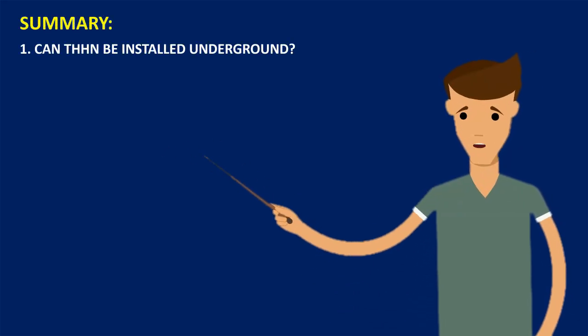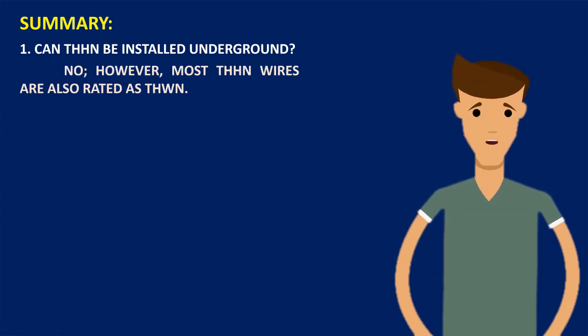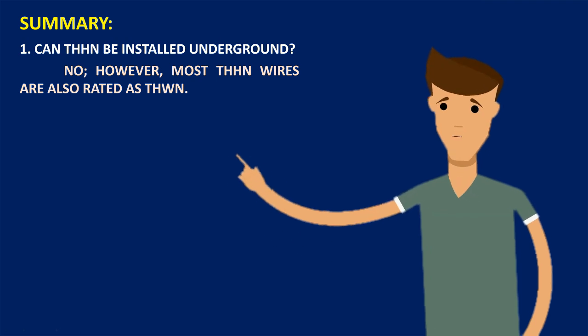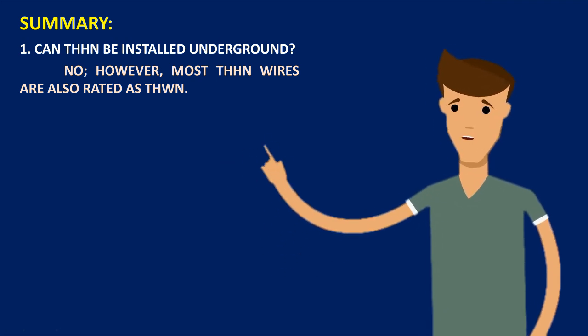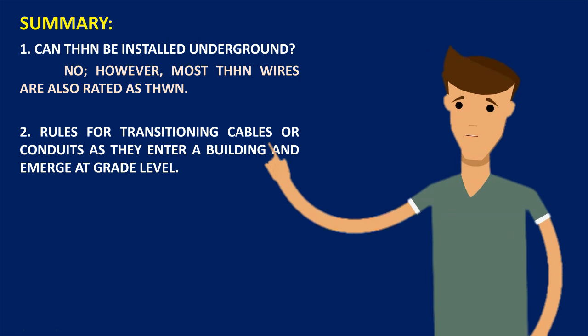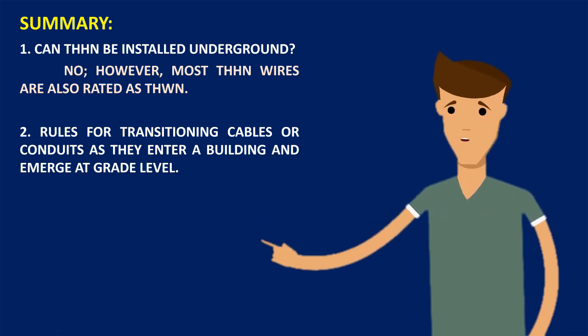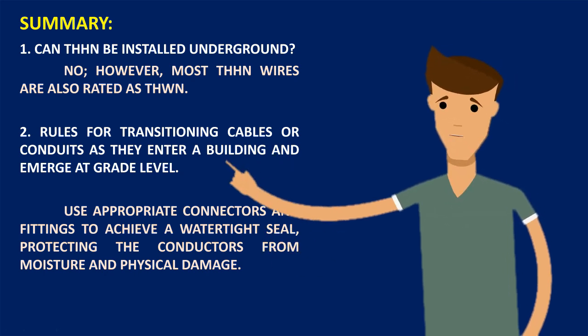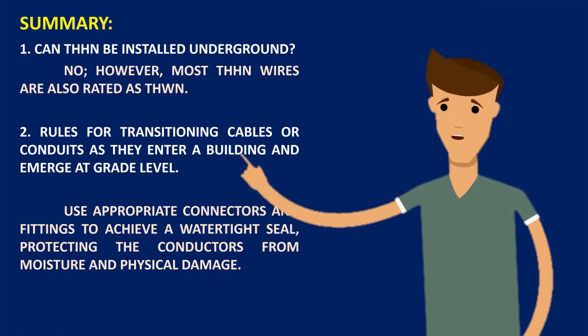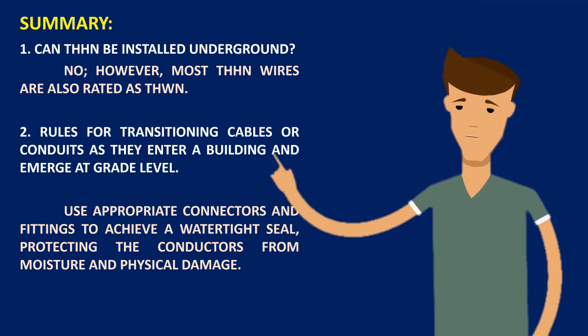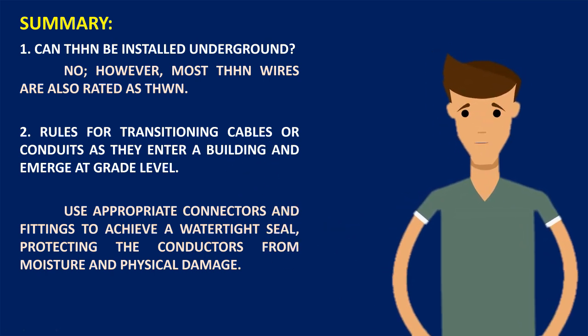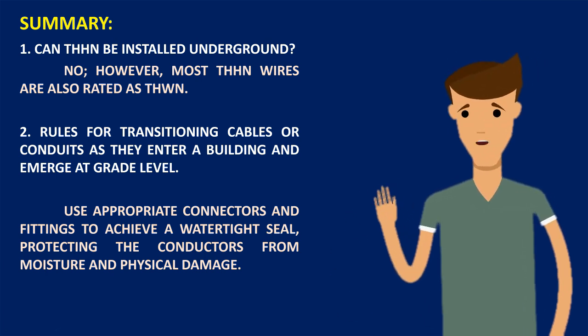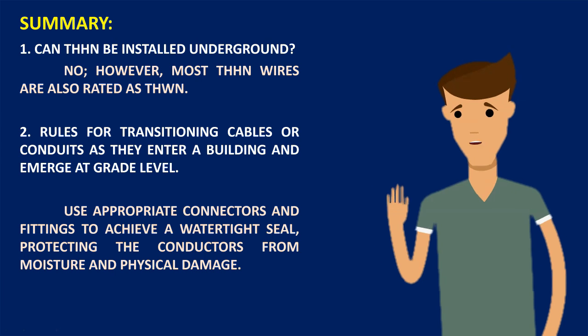Going back to our question: can THHN be installed underground? The answer is no; however, most THHN wires are also rated as THWN, so it's important to ensure that the wire is marked with the appropriate slash type. Additionally, we discussed the rules for transitioning cables or conduits as they enter a building and emerge at grade level. Use appropriate connectors and fittings to achieve a watertight seal, protecting the conductors from moisture and physical damage. When installing wires underground, consider using conduits for added protection against physical hazards and environmental factors. Thank you for participating in this important discussion, and let's continue to prioritize safety in all our electrical projects.